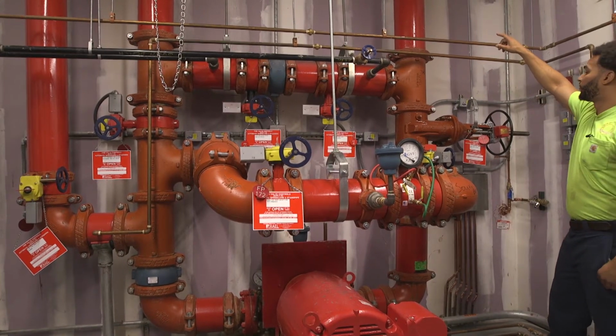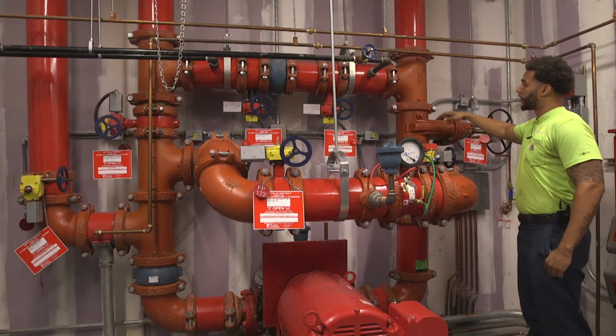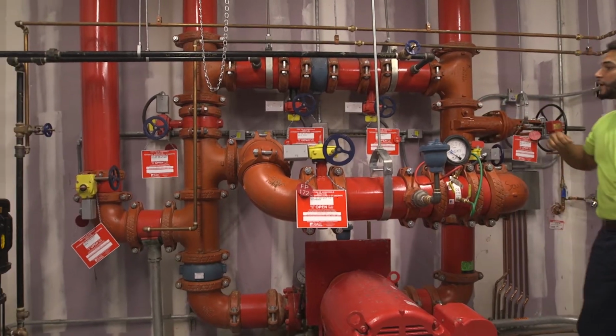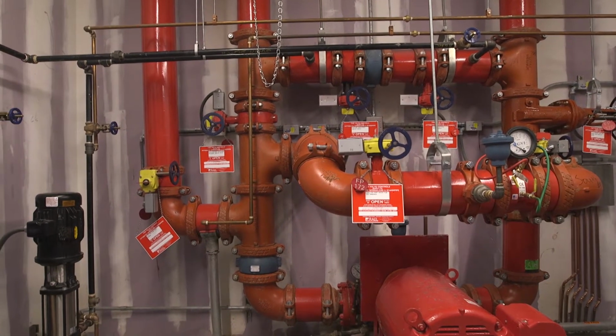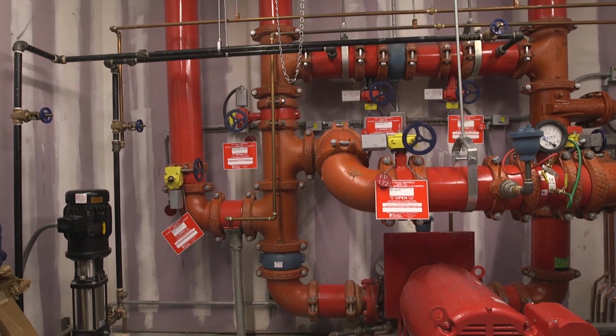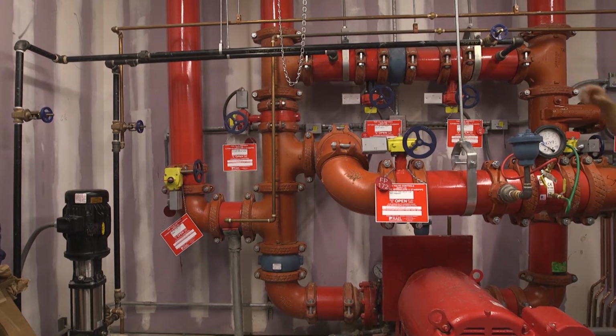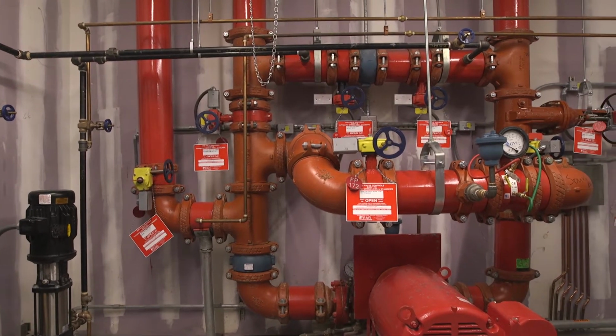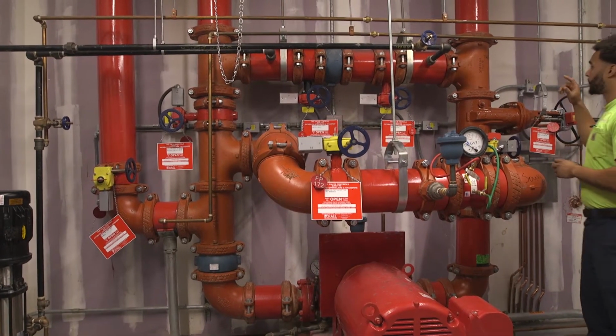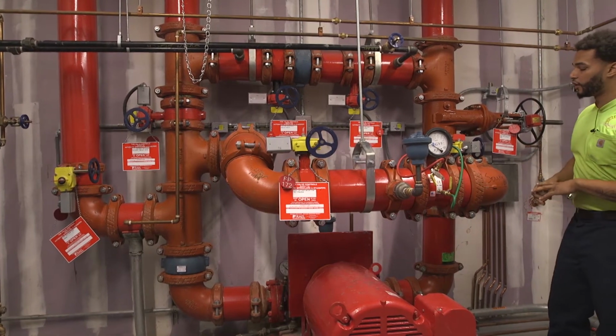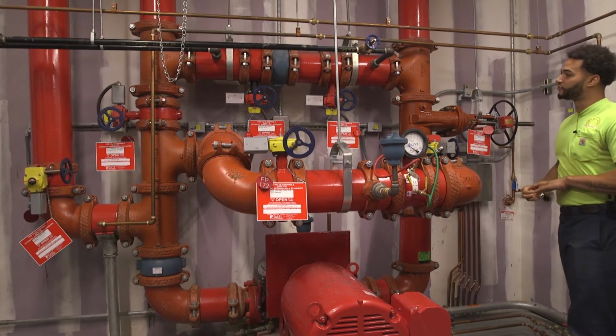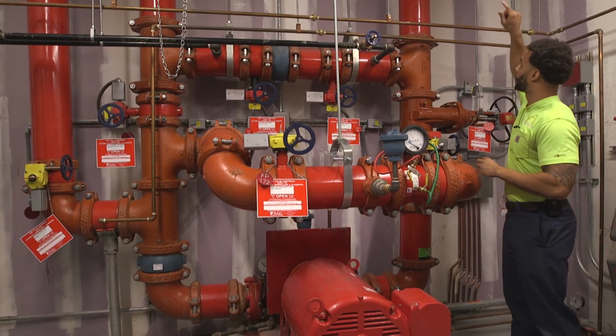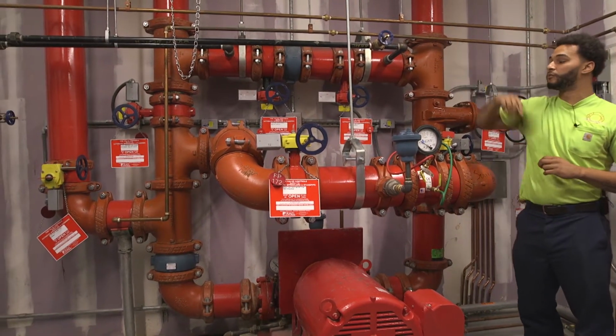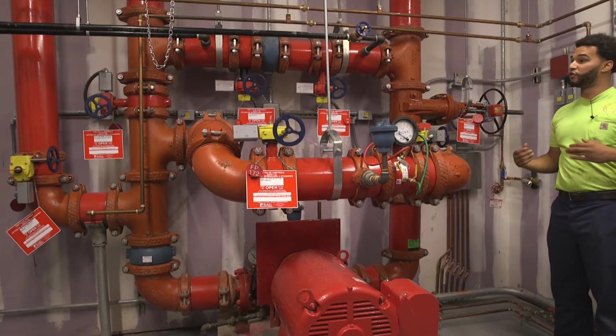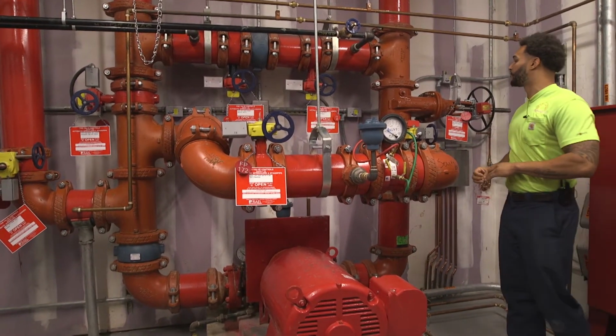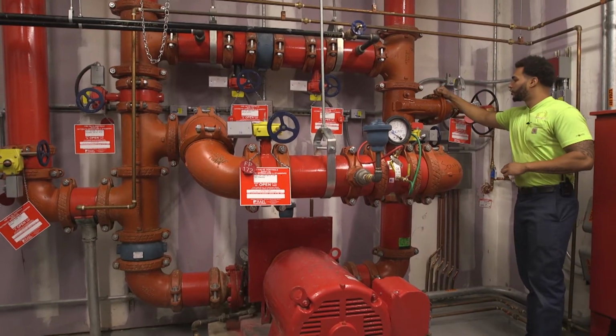Before the street service goes into the fire pump, the first thing it travels to is your fire pump bypass line. This fire pump bypass line is made up of 2 isolation valves, which are butterfly valves, and 1 check valve. This check valve is going to allow water to flow in one direction and prevent it from flowing in the opposite direction. So say, for instance, if we had a power outage in the building and the fire pump wasn't able to operate for whatever reason, you're still going to have your street service coming in and still feeding your system at about 63 pounds, which is what we currently have coming into the suction side of the fire pump.